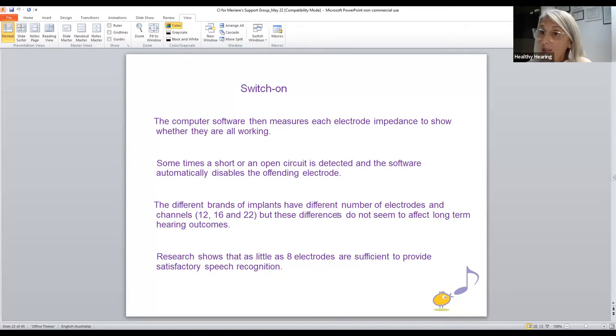Sometimes there's problems with electrodes. You can have a short circuit, you can have an open circuit, and the software will find that out. And if that's the case, it will automatically disable the offending electrode and no harm will be done to either patient or the device. All the research has shown that even if you disable a lot of the electrodes, as long as you're left with 8 electrodes, the end result can be quite all right. So no panic if some of the electrodes don't work at time of switch on. It happens, not all the time, but it can happen and it's not a big deal, okay?